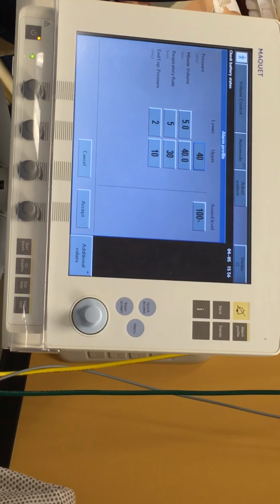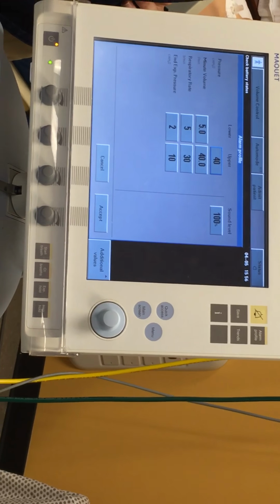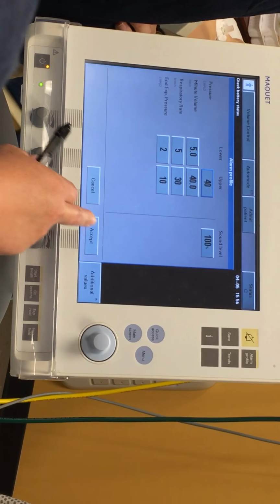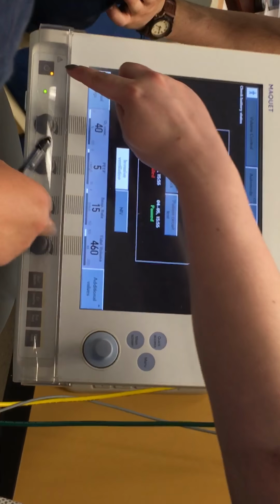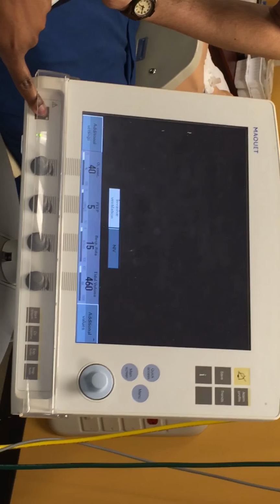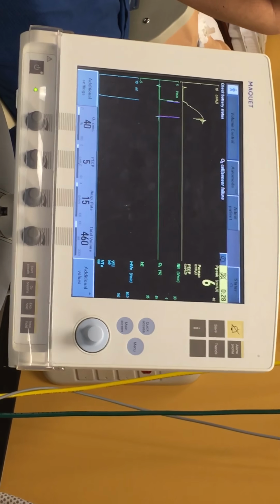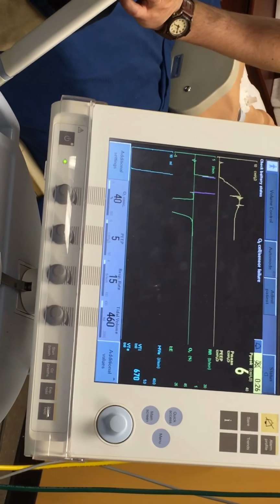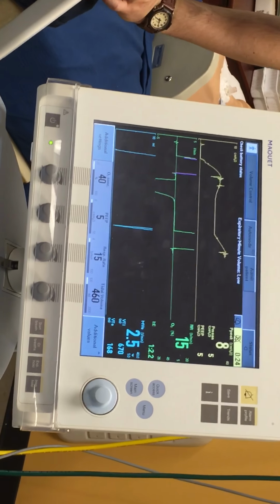Well, we have to look at the pressure first, right? Wait a couple of minutes, let it cycle for a couple of minutes before you set your alarms. So you hit the start. That's how you start it. Power button to start. Go ahead. Are you doing SIMV or volume control? Volume control right now. Okay.